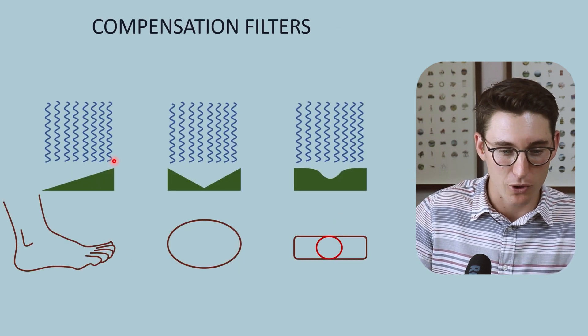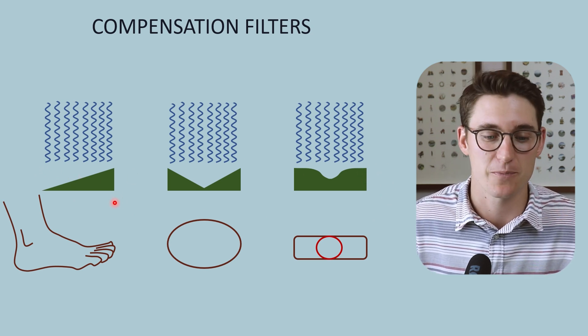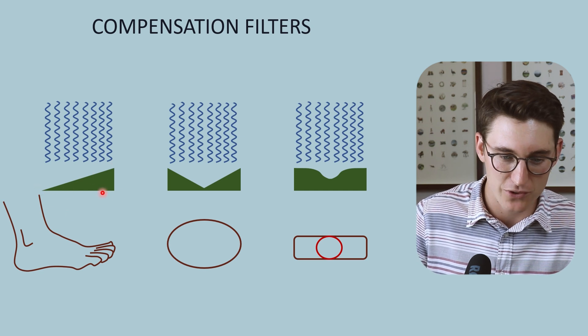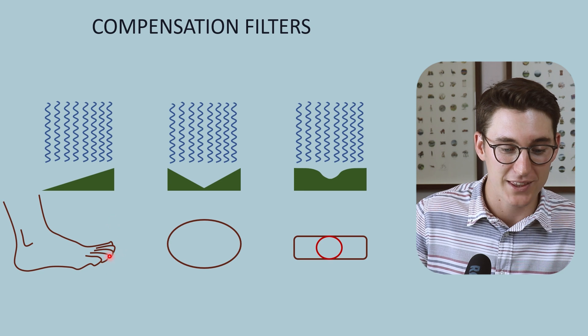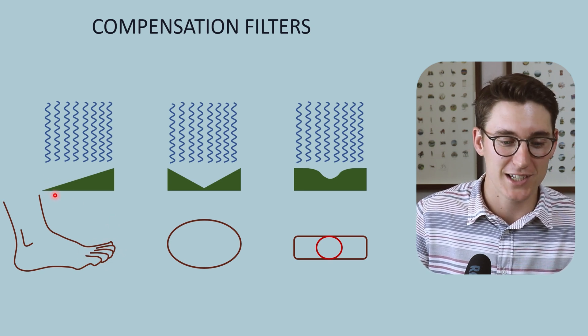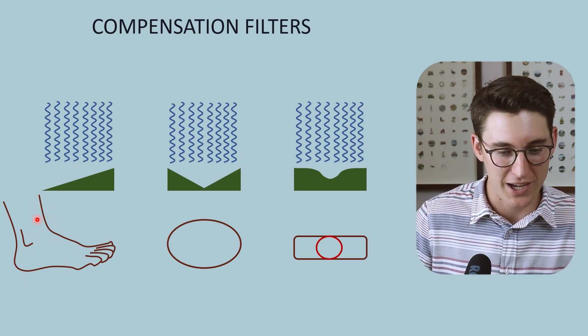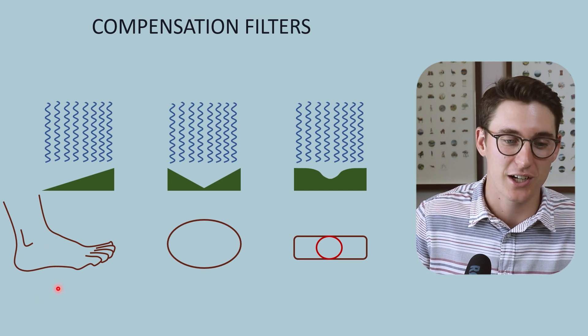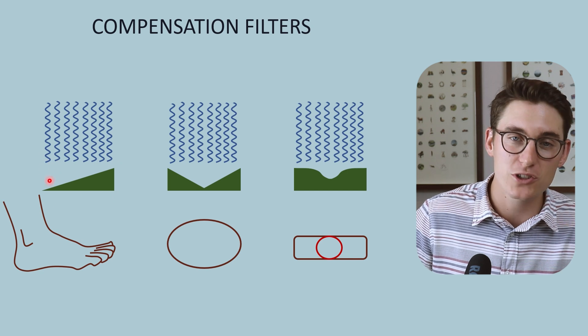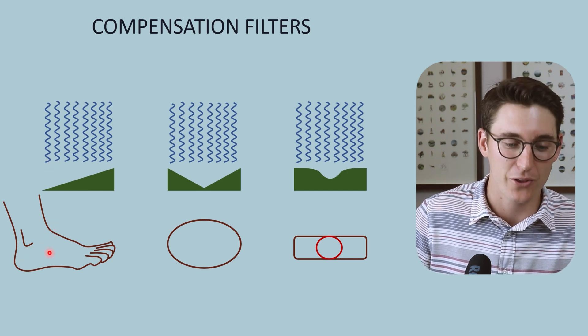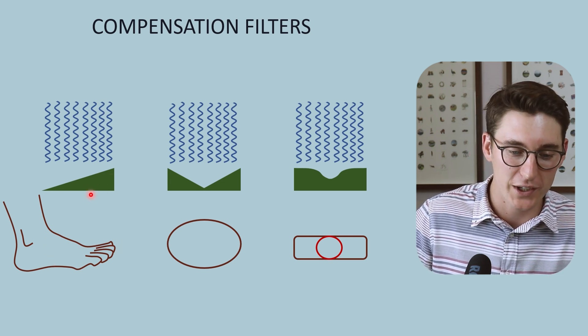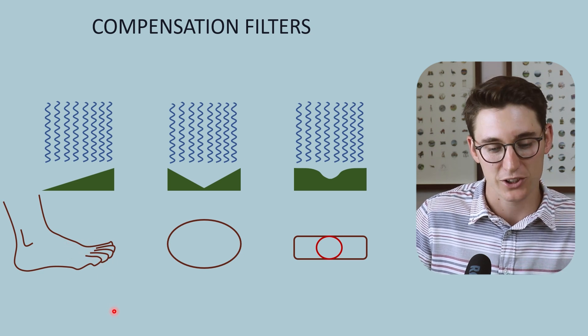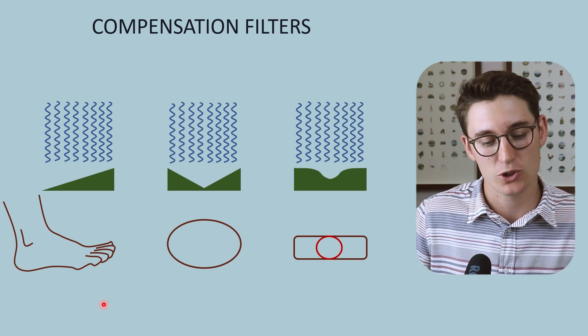We can also add a special type of added filtration known as a compensation filter or equilibrium filter, designed to produce an even exposure to our x-ray detector. A wedge filter attenuates more of the beam over the thinner part of the patient and allows more beam intensity through over the thicker part. For example, with an ankle and foot, the ankle is thicker and attenuates more x-rays. The wedge filter allows most x-rays through over the ankle and attenuates more over the thinner toes and forefoot, giving a more even exposure to the detector.